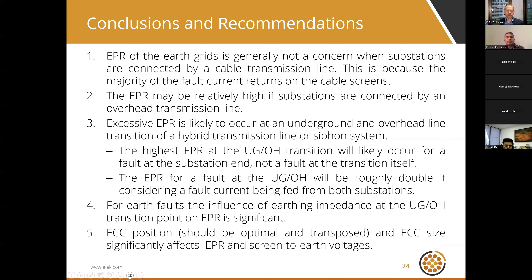In conclusion: EPR of earthing grids is generally not a concern when substations are connected by a cable transmission line. In the simple example modeled, 96% of the total earth fault current returns via the cable screens and does not cause an issue at the local earthing system. This is because the majority of the fault current returns on the cable screens, which makes earthing designs powerful and straightforward.